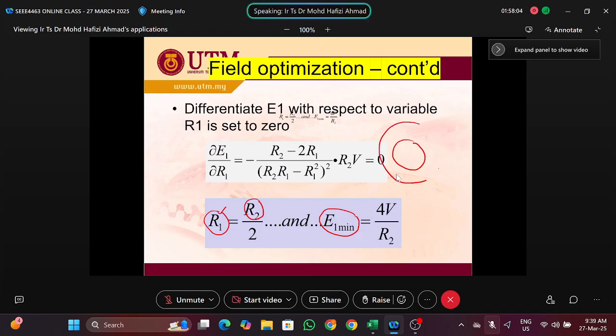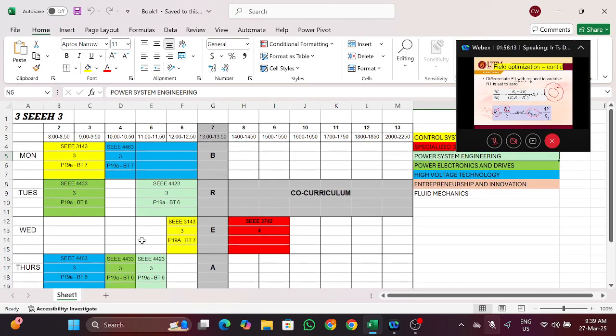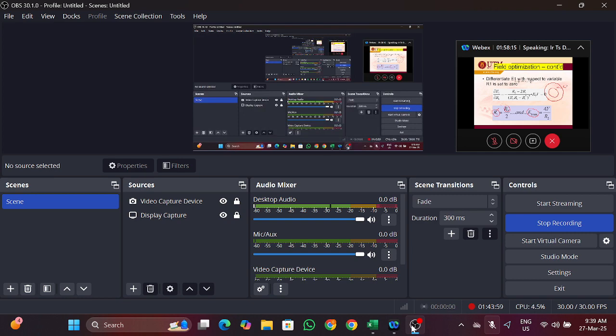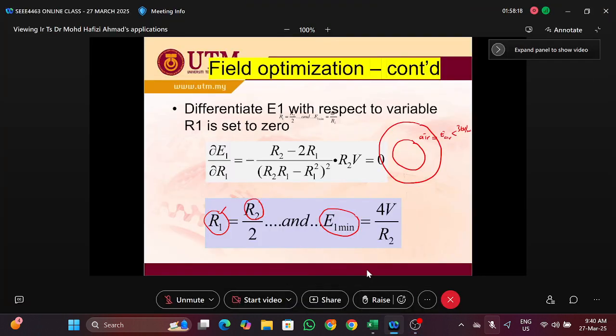The idea is like this: between the inner and outer radius we fill with air, and we know the electric field of air cannot exceed 3 kV per millimeter. So we need to design suitable R1 and R2 so it doesn't exceed that limit. If it exceeds the dielectric strength of air, it can cause flashover, leading to a short circuit between the inner and outer electrodes.